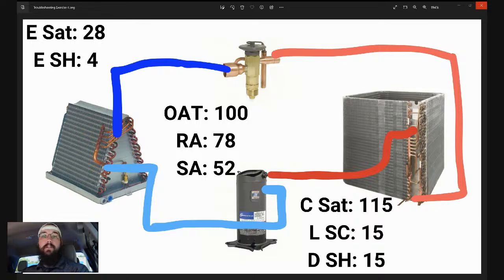Then you take a walk around the space, and you're looking at the actual registers. So let's just say they had ceiling registers. All the ceiling registers are open. Nothing's plugged up. Nothing's in front of any of them. Everything's flowing. Reminder, we have a data point: our external static went from 0.8 to 0.9 when we went to high fan speed. So we increased external static as well.